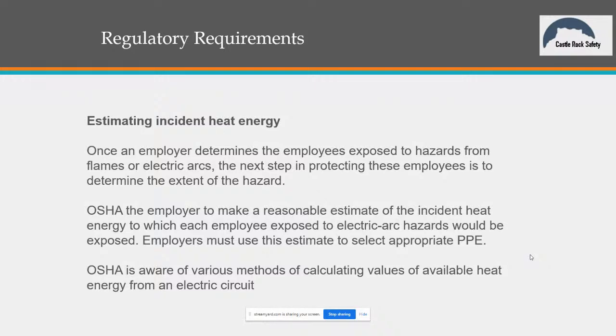On the supply side, we perform calculations. We go to 1584, and we got to know our short circuit current. We got to know clearing times. We have to know what size is the box. Now we got to determine electrode configuration. 1584 has been revised, so there's a lot more data that we have to have. It's not as complicated on the utility side.